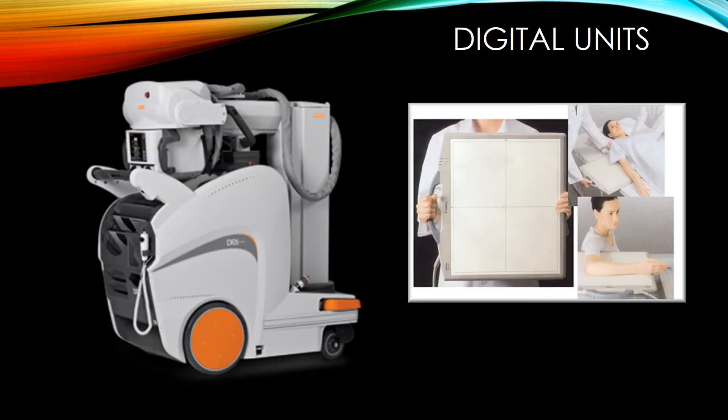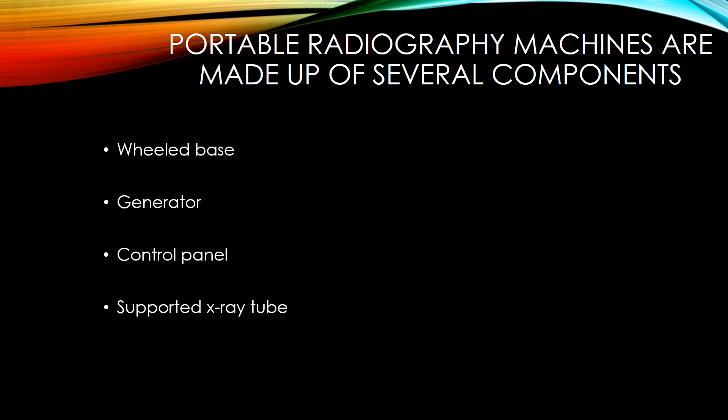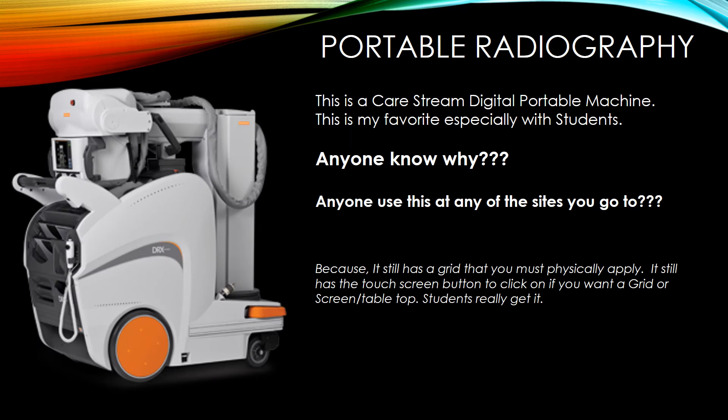Digital units: portable radiography machines are made up of several components — a wheeled base, a generator, a control panel, and a supported x-ray tube. This is a CareStream portable machine, which is a favorite especially with students because it still has a grid that you must physically apply. It has a touch screen button which you click when you want a grid, a screen, or tabletop technique, and students really seem to get it.